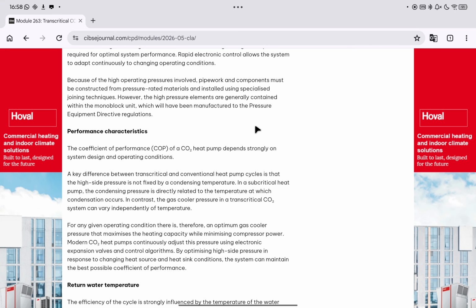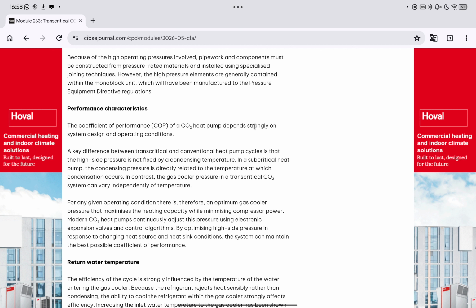Performance characteristics. The coefficient of performance, or COP, of a CO2 heat pump depends strongly on the system design and operating conditions. A key difference between transcritical and conventional heat pump cycles is that the high side pressure is not fixed by a condensing temperature.